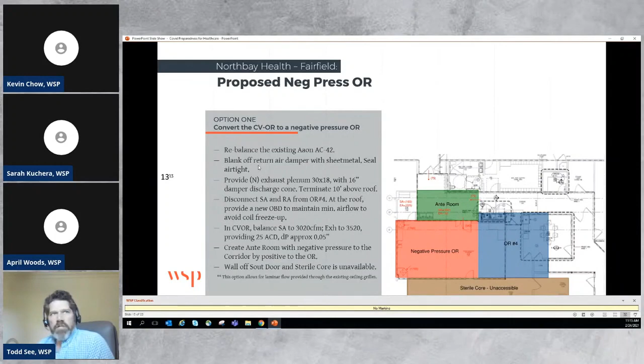And so what we did was, working with the hospital and the existing facilities, we were able to reconfigure an air handling unit that serves this area specifically by closing off the return air damper, using that fan, putting it into exhaust mode. We added HEPA filtration on that exhaust and a stack to take the exhaust up and away. We converted this into a 100% exhaust system without any return air.